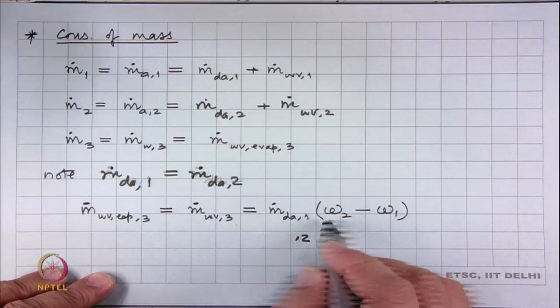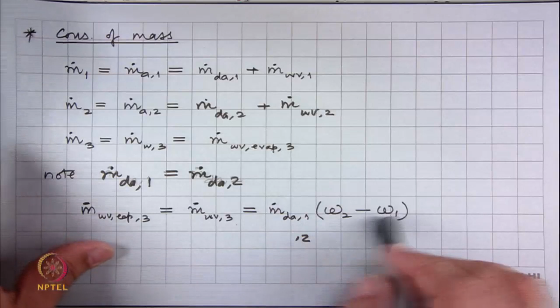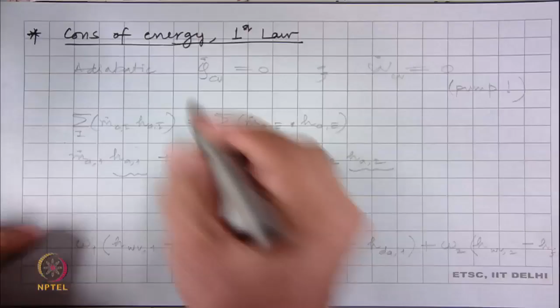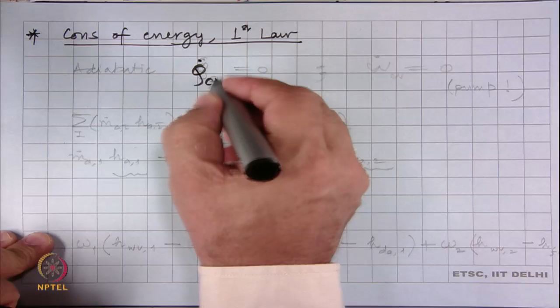Now, because the mass flow rate of dry air has not changed from inlet to outlet, we can say that m dot dA 1 is equal to m dot dA 2, and so mass flow rate due to evaporation, which is m dot 3, is m dot dA 1, or it could be m dot dA 2, multiplied by omega 2 minus omega 1. Omega 1 and omega 2 are the moisture contents of the air. So, these are absolute numbers, this is not a fraction. We now apply the conservation of energy with already having said that Q dot CV and W dot CV are 0.